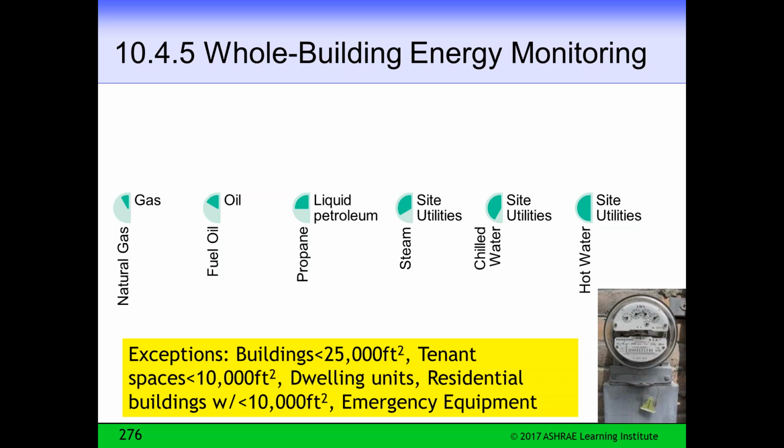So you have to have a 15-minute meter on all the commodity type energy. So that's what we've done. And you know, some of it might seem like overkill, but most of these would have 15-minute meters on them anyway. Probably natural gas wouldn't, and most people know it goes into the boilers and stuff. But anyway, it is a requirement to have the 15-minute meters on all these energy sources, with a few exceptions.